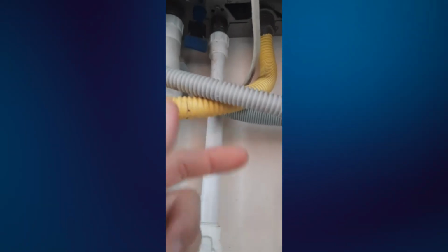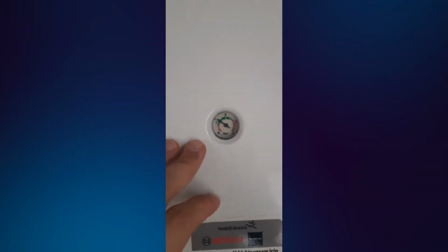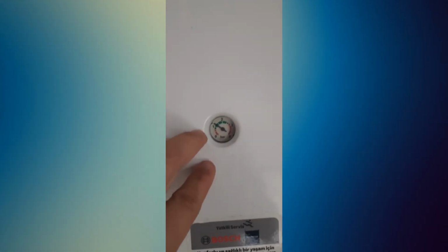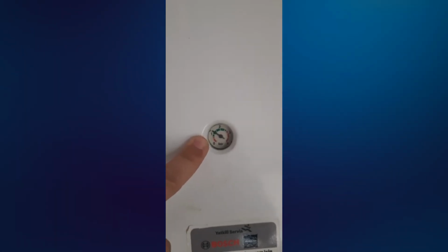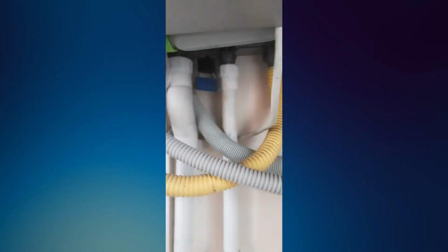After restoring pressure, reset the boiler once, following the instructions for your model. A reset can clear a temporary lockout, but if error 2951 comes back, do not keep resetting the boiler again and again. Repeated lockouts mean the boiler is detecting a real fault.